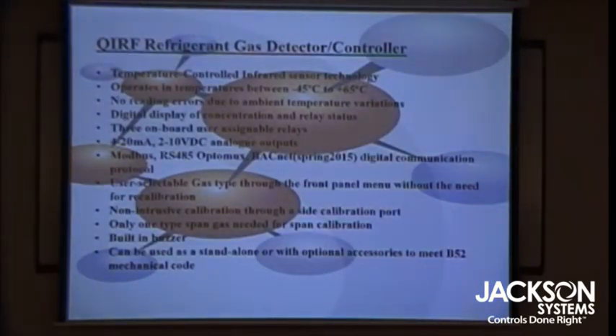And the other problem in freezer applications, because they're typically very humid, as soon as it would come inside the room, you could have humidity problems in the solenoid valves. So what they were using were molecular sieve dryers, and then that kind of affected the reading in some applications. So by this now, you have it in situ, you just run your cable to it, and you have real-time monitoring of all the sensors.